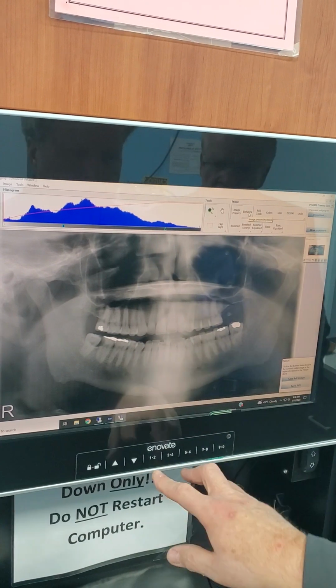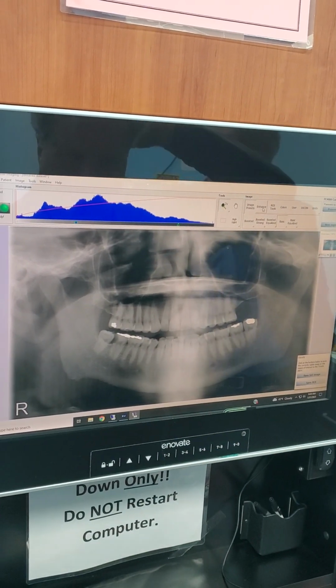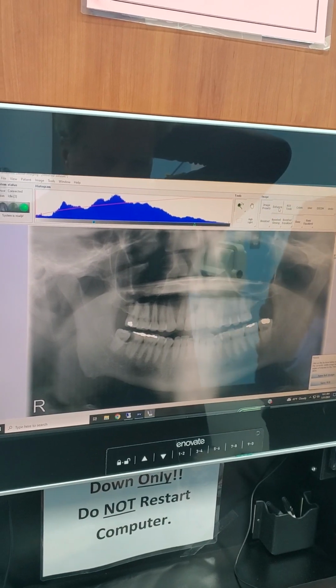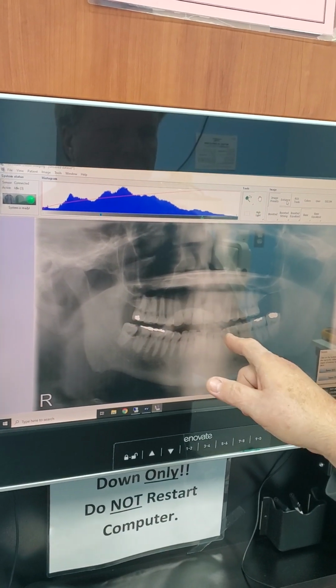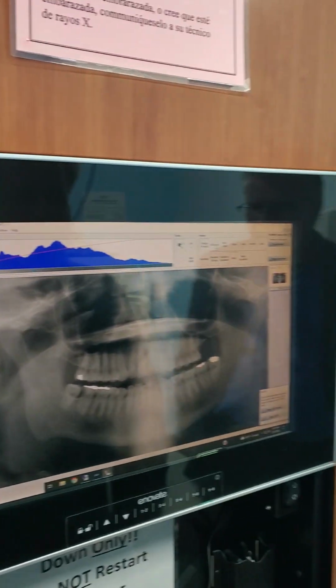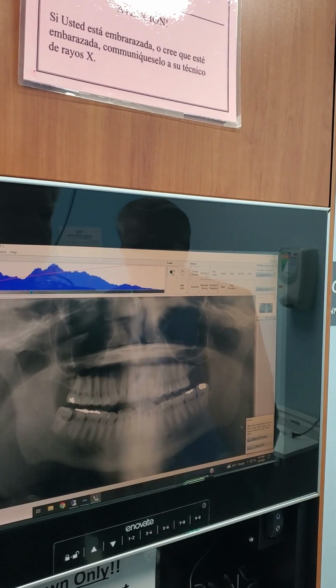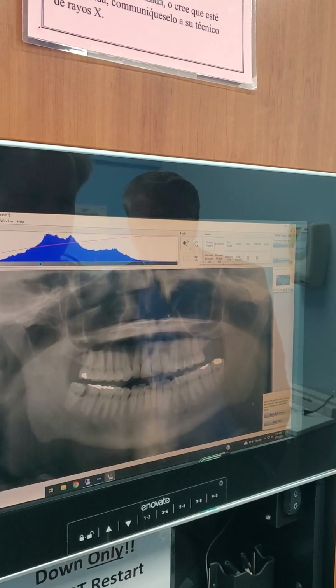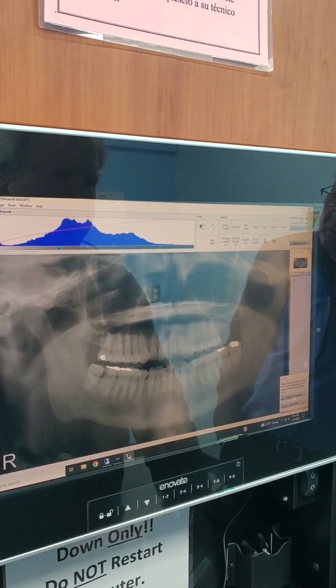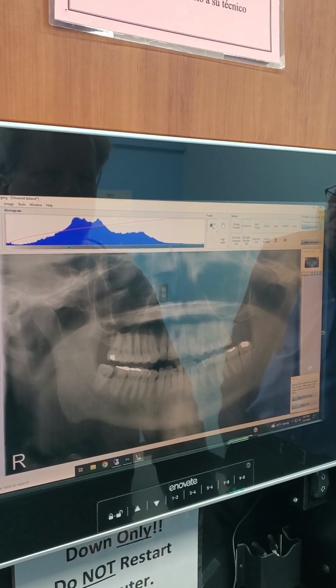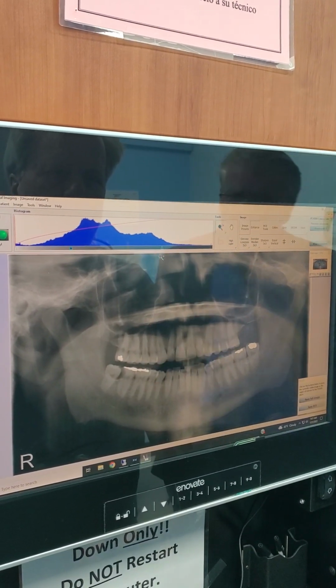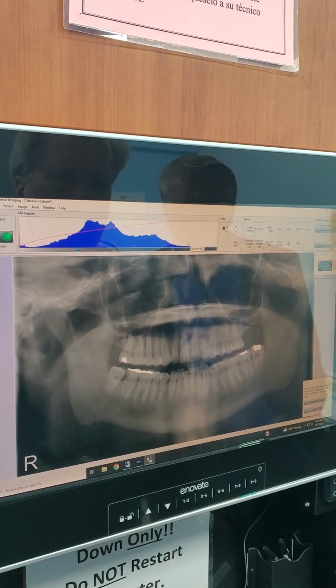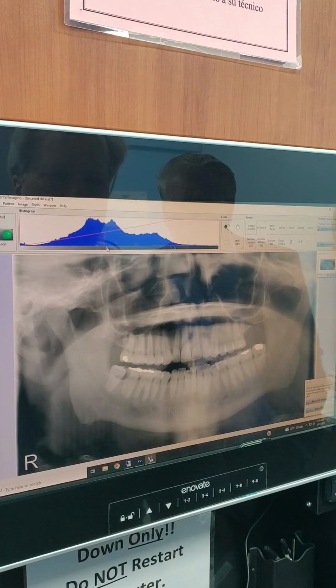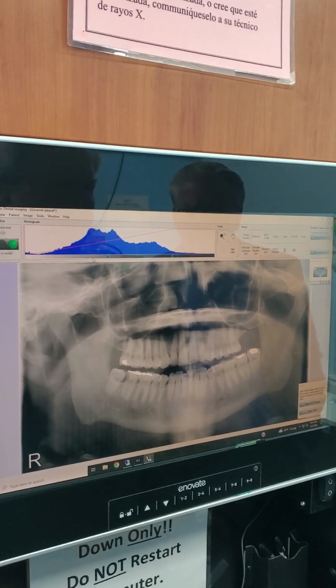Right. Okay. And this is spinal ghosting. When the beam comes around the back side of the patient, it goes through the base of the skull, and it has to pass through the cervical spine. So this is common. That's especially what you see if the patient is slumped, it's going to be accentuated. And this equalization tool will minimize that and improve that. And is that an automatic thing that happens? It can be set to be automatic. In other words, you can set your histogram to a certain setting. They say to put this slider in the valley of the mountain and to put this slider at the peak of the mountain to get close to what your image should be.